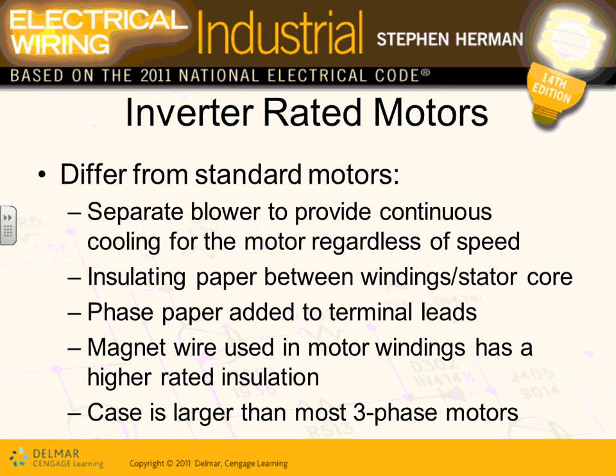You're going to hear this all the time. When you're an engineering firm and you go to the air handling unit, rooftop unit, when you read the specification by the mechanical engineers, they will say the manufacturer must provide inverter-rated motors. Now, what the heck is an inverter-rated motor? It's a specially designed motor, same as an induction motor, but more robust, fat, fluffy, that can handle the heat generated by driving it with a VFD. That's all. So remember that one.